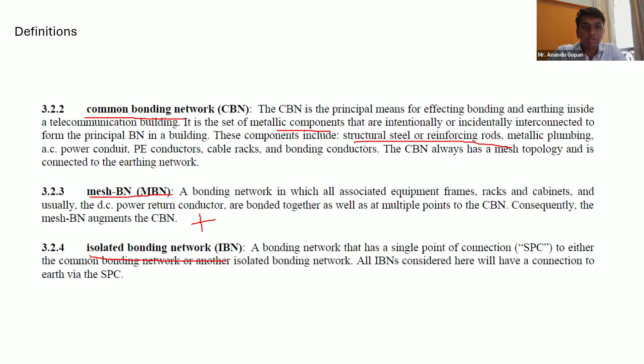I talked about the RBC, right? The rack bonding conductor. With this rack bonding conductor, you will be connecting your cabinets and your rack metallic parts. All of these dead metallic parts you are supposed to interconnect, and you will form a mesh bonding network. And then you will have your isolated bonding network. Basically, an isolated bonding network is just like a mesh bonding network, but instead of multiple points to your common bonding network, it will be one single point. You'll call it a single point connection.